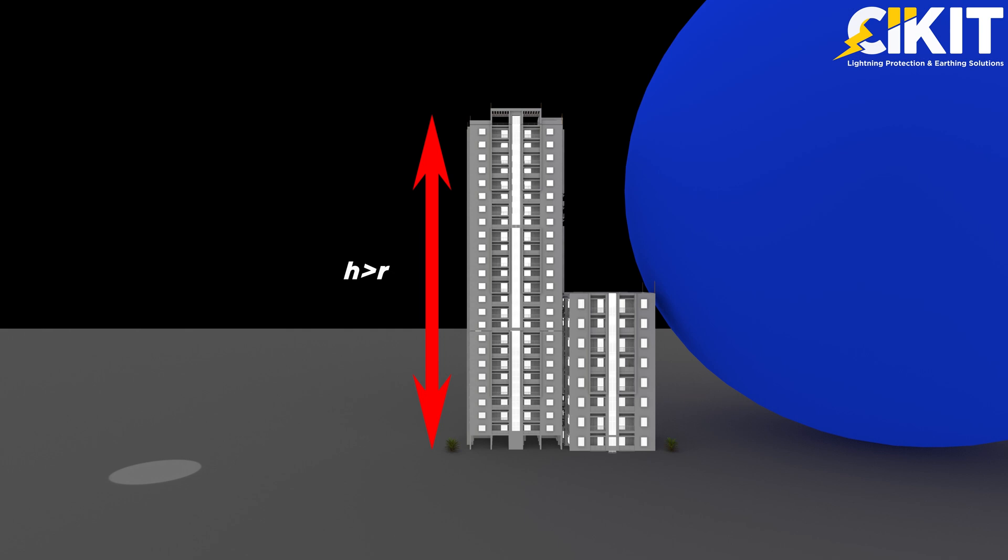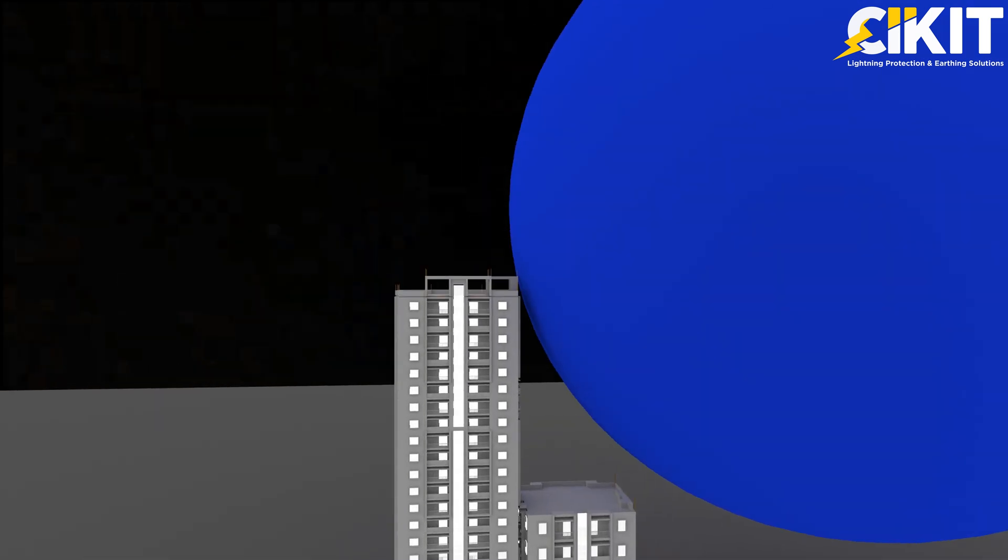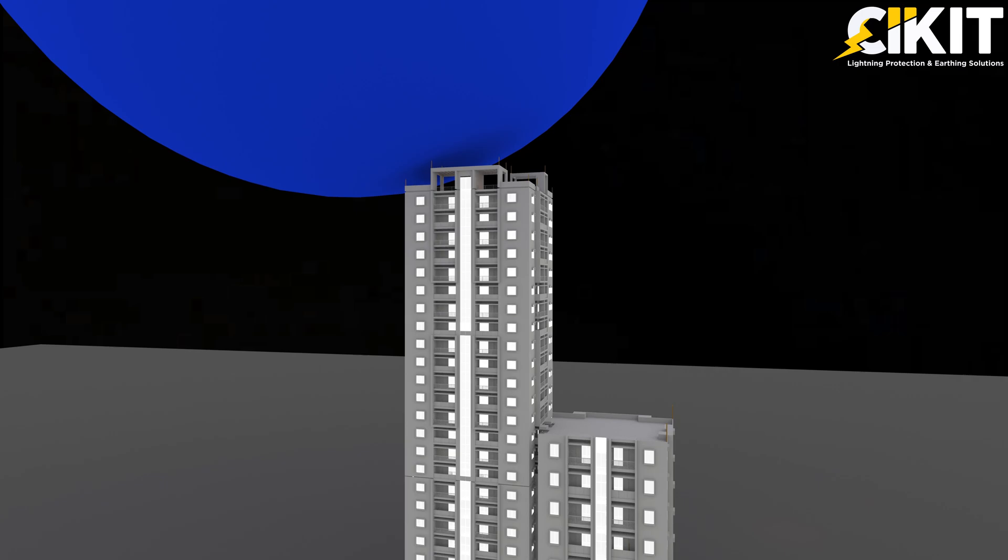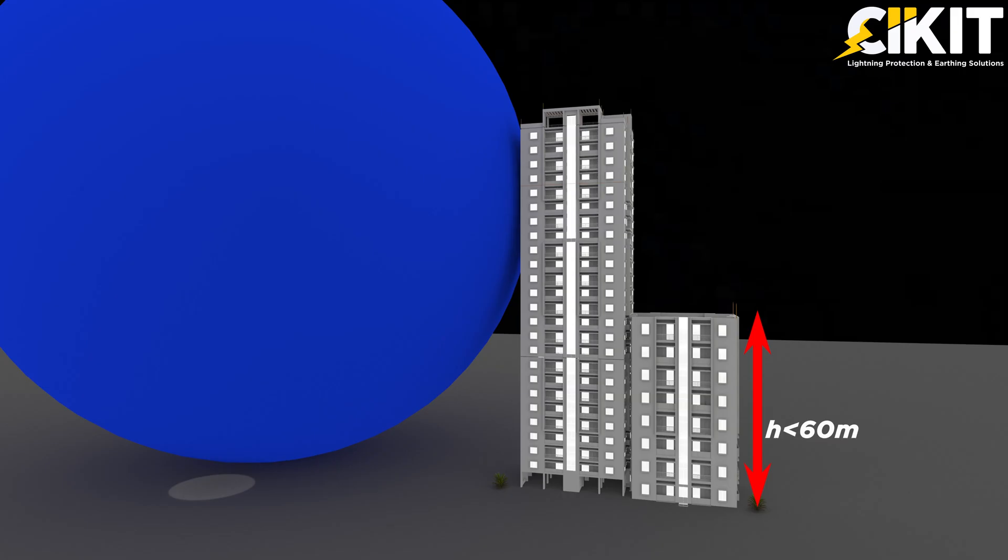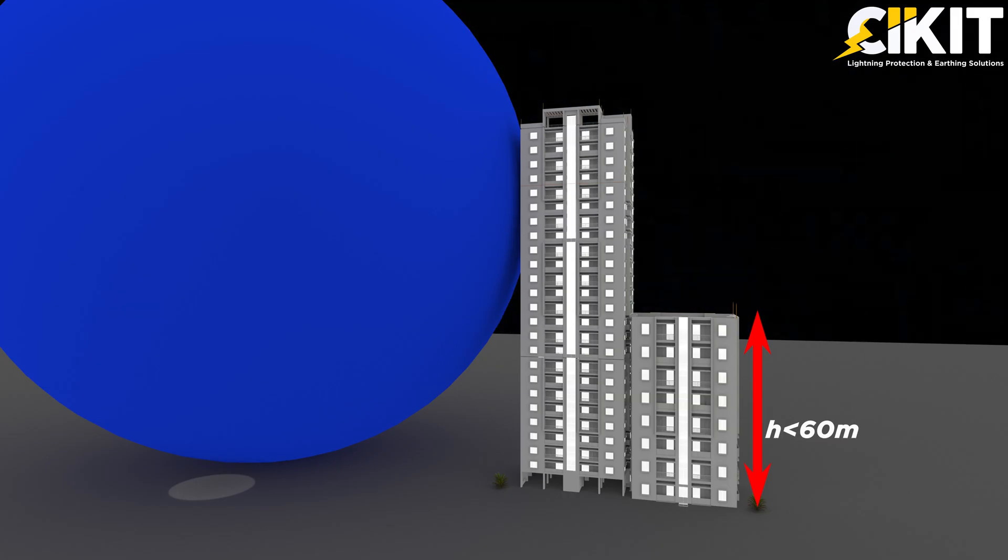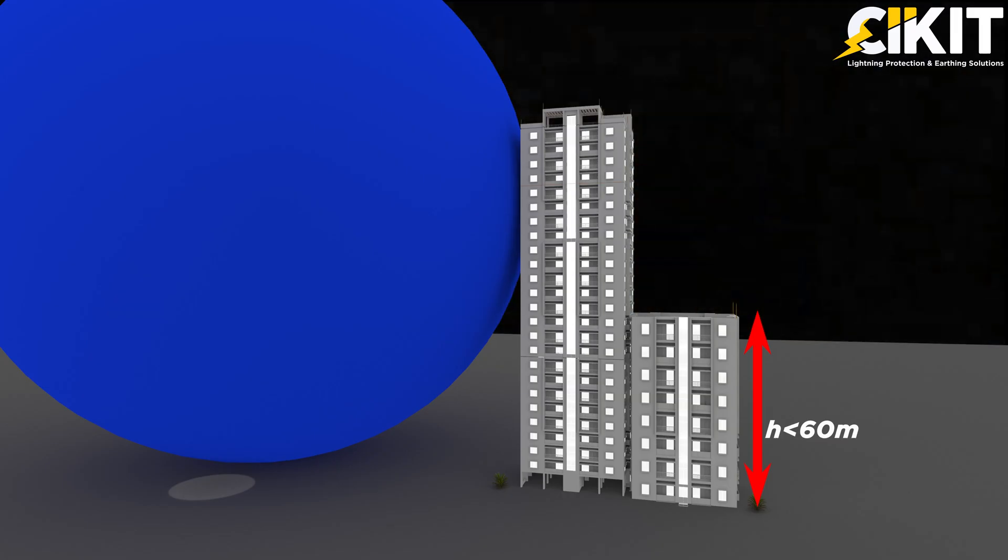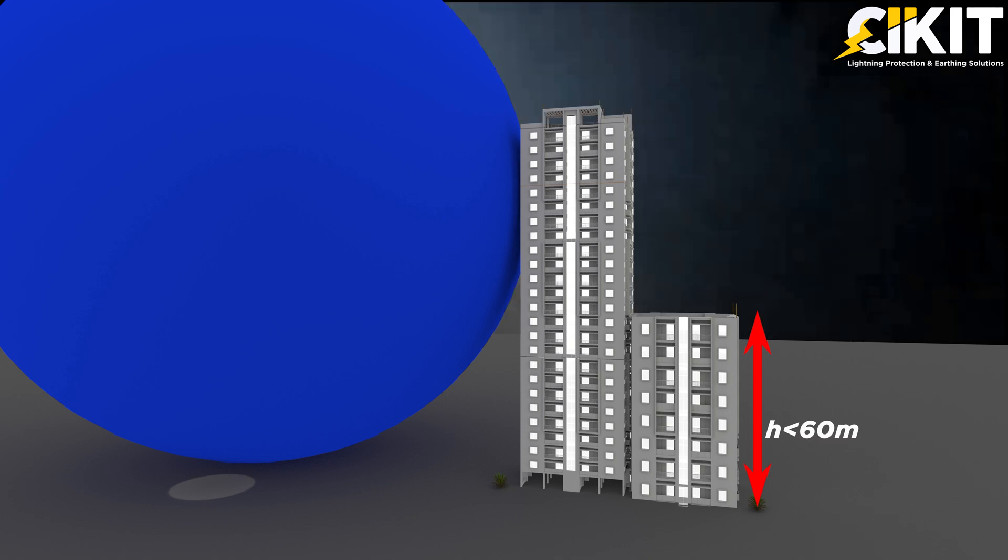If the height of the building is greater than the radius of the sphere, then the lightning may strike on the side of the building. But the probability of side flashing on buildings of height lesser than 60 meter is very low.